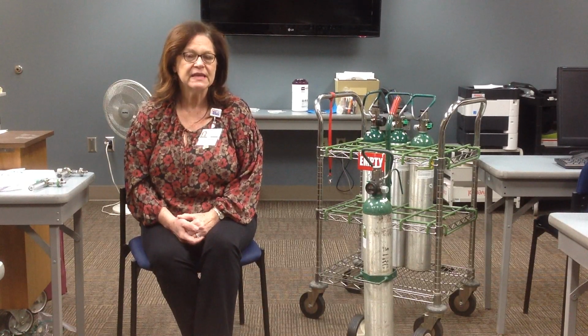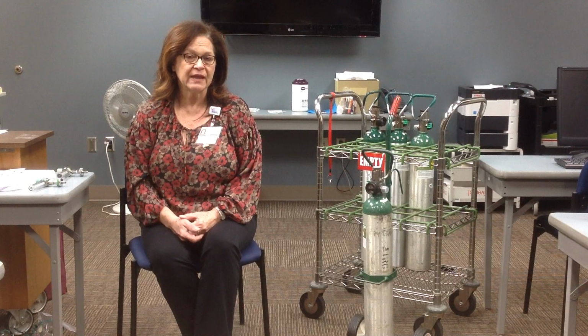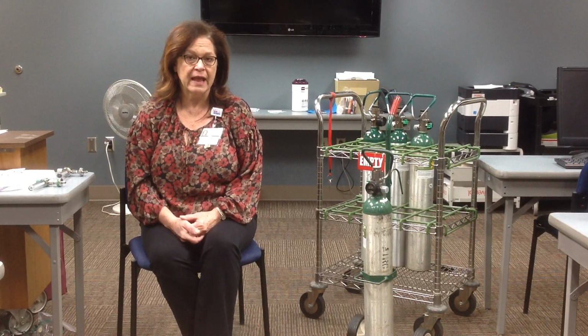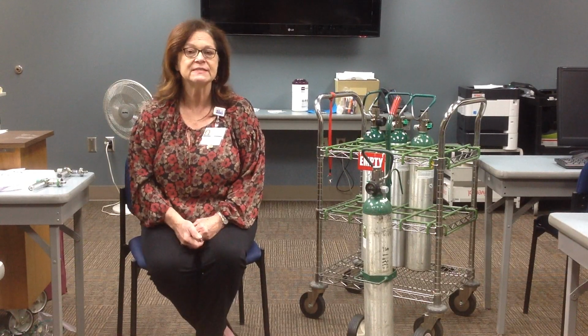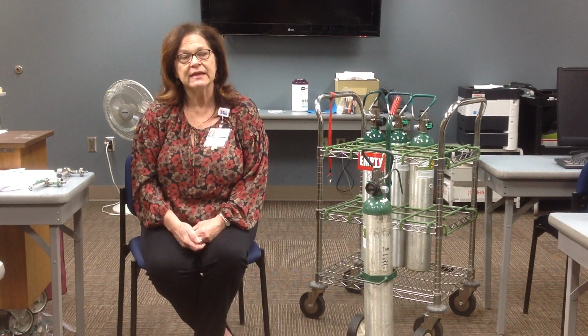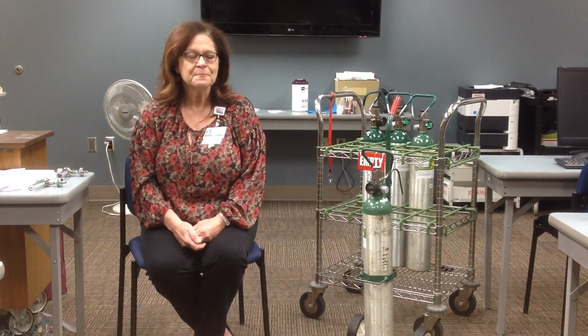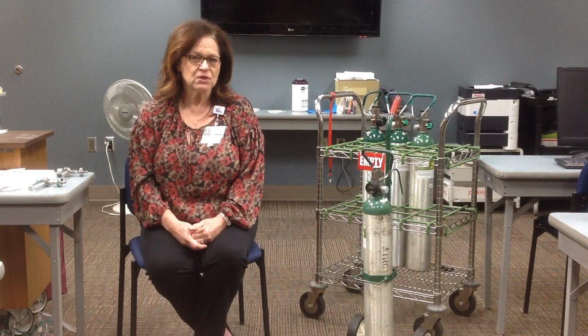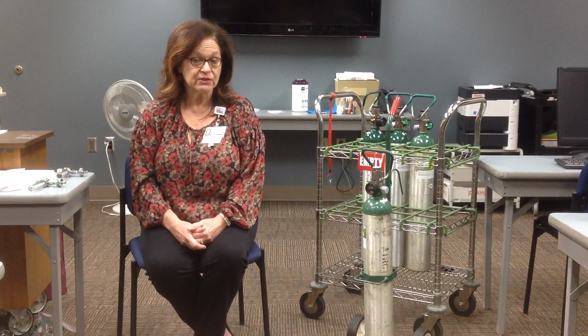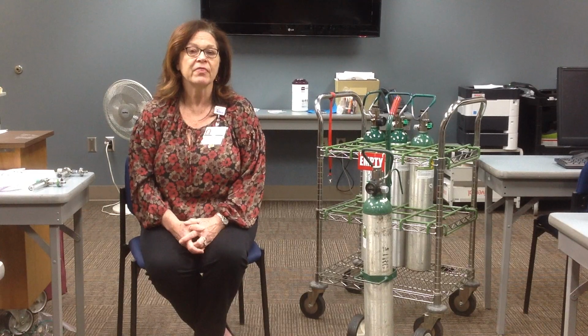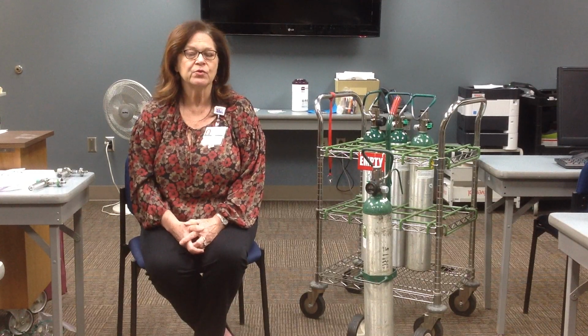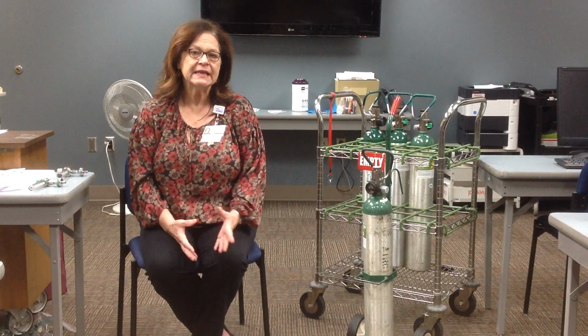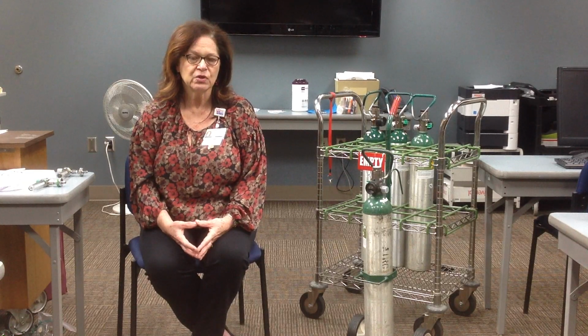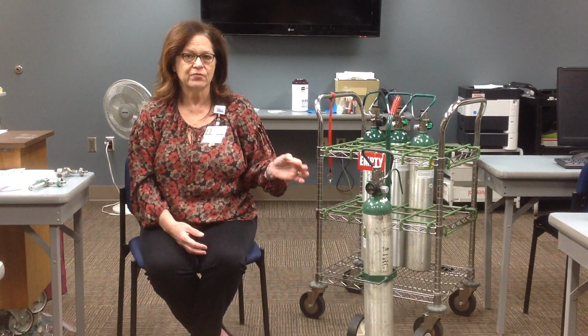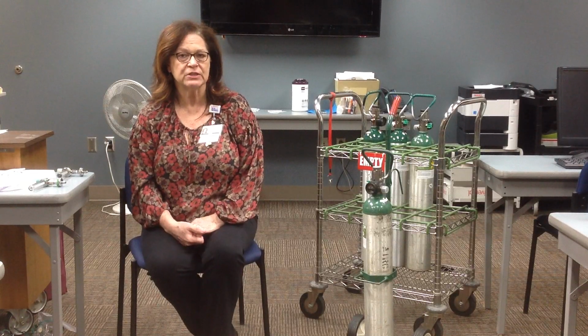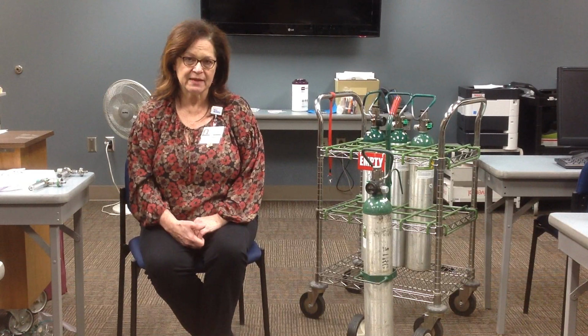and you can see this. If we can put them on the high-flow nasal cannula, sometimes we can stop them from tiring out and either going on BiPAP or getting intubated. We did a trial in SICU a couple years back, and every patient in the unit that was on 3 liters a minute nasal cannula or above went on the OptiFlow. With the OptiFlow, you can titrate the flow rate independent of the FiO2. So you could have a patient on from 21 to 100% oxygen and from 10 to 60 liters a minute.